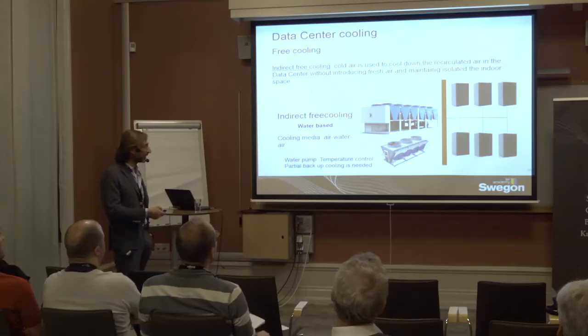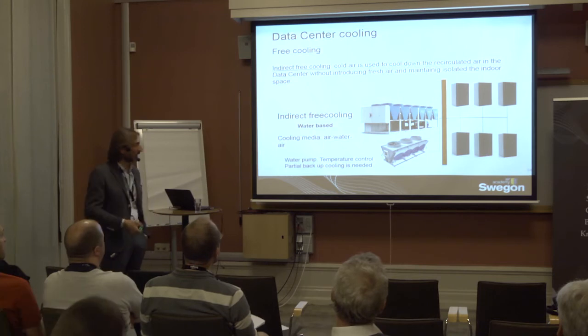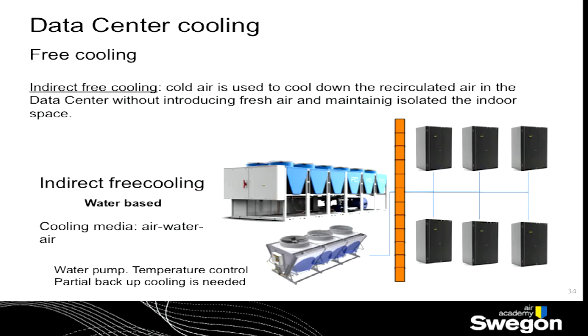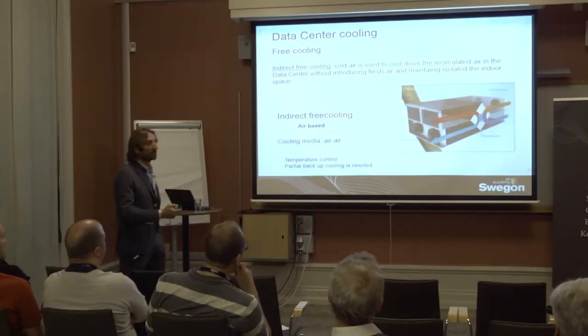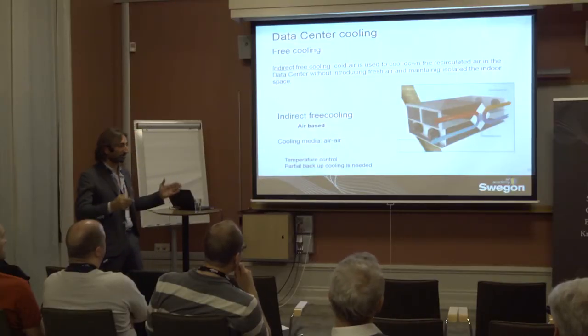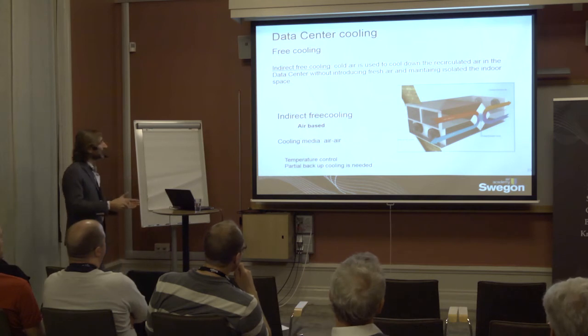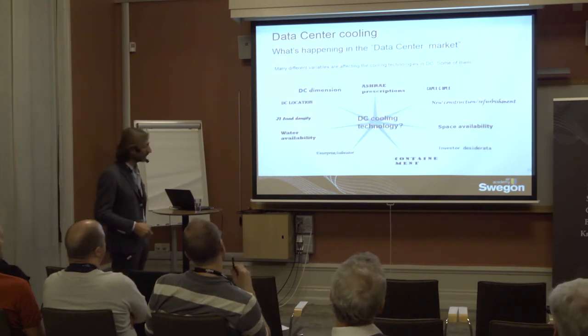And you can have an indirect free cooling, water-based, so you have a chiller equipped with a free cooling section, or you can use a dry cooler outside to maximize the performance in free cooling. And you have to use the rack, the CRAC inside, equipped with a free cooling system, of course. Or you can use an indirect free cooling air-based, so the exchange happens air to air. So you can divide by the media. In this system you use only air, in this one you use air to water and to air, and in this you use air to air exchange. So you can classify it in terms of the media that you use to transport the cooling.